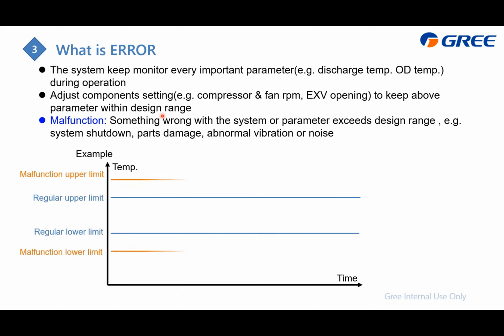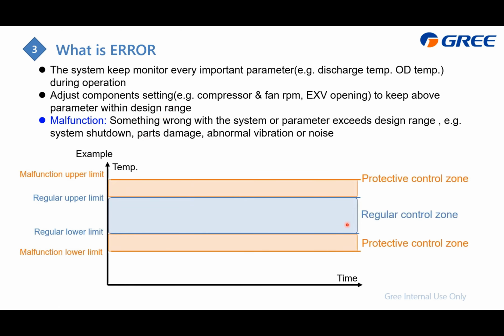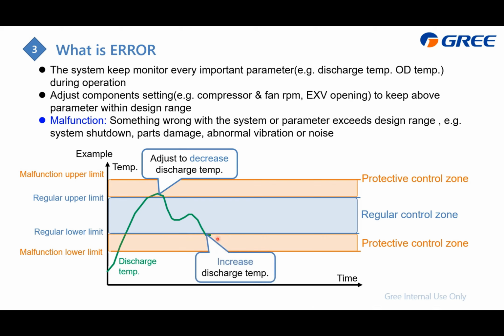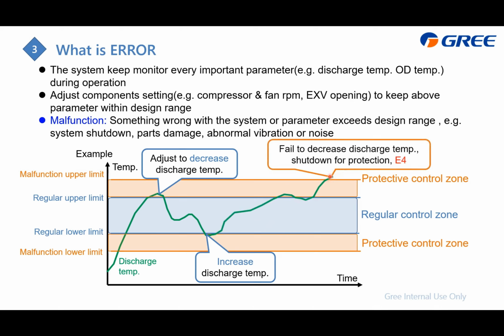For every important parameter, we already set up the regular control zone and also the protected control zone. For example, take the compressor discharge temperature. If it is higher and enters this protected zone, we will adjust parameters, like decreasing the compressor RPM or increasing the EXV opening, to make it go down. And if it is lower than the regular lower limit, we adjust the parameters to make it higher. Once it is in this zone, the system will not do any protected control. But if it goes out of this protected zone, the system will have no choice but to shut down and display the error code, which is E4.